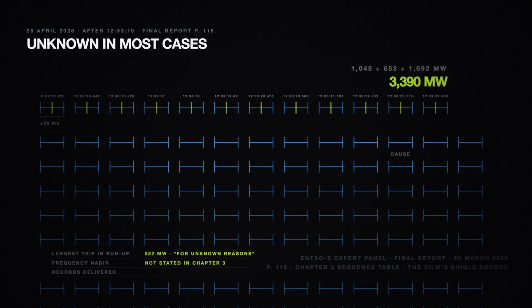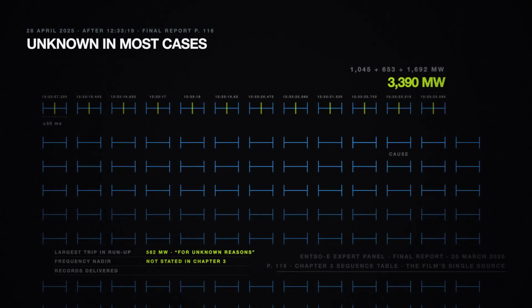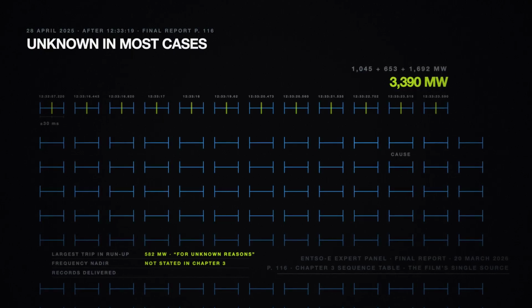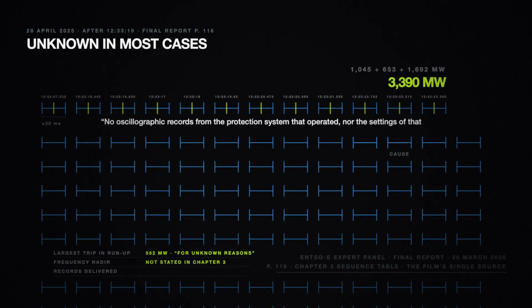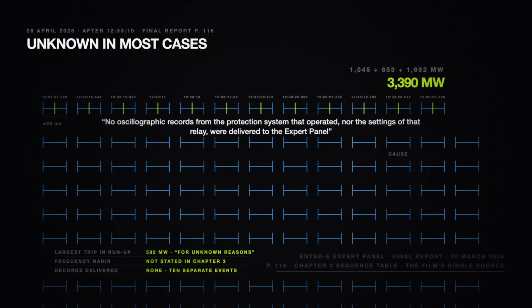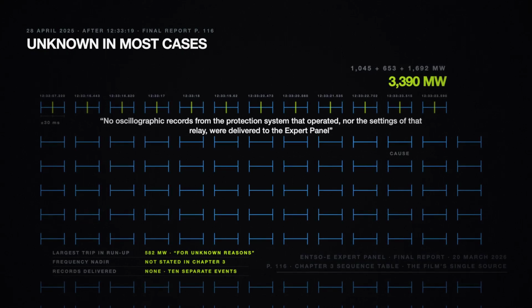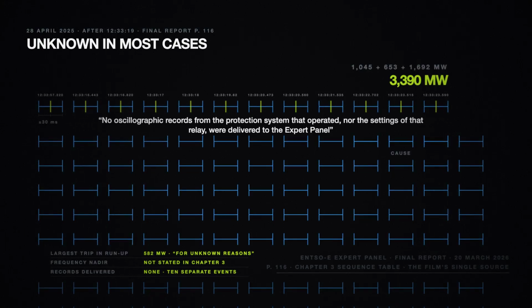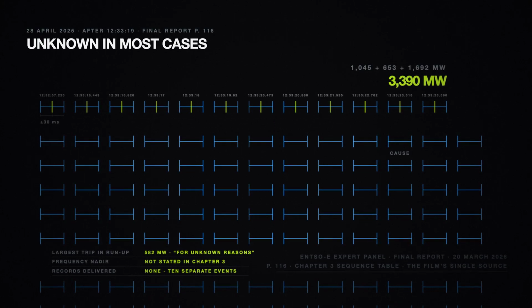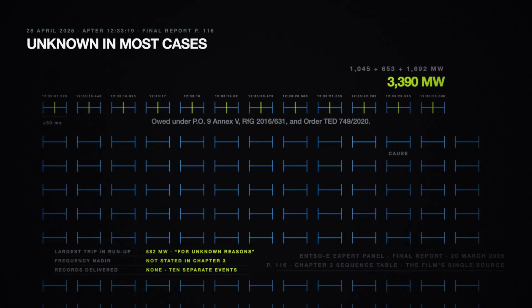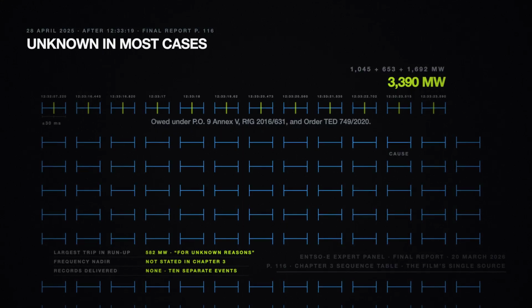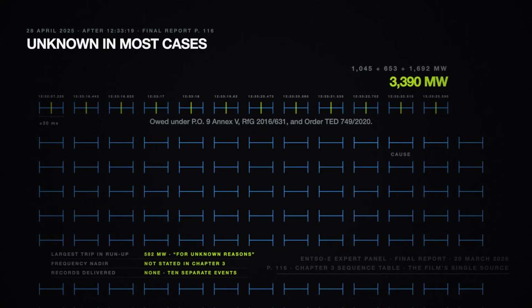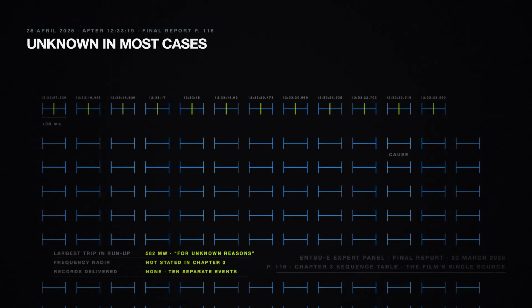This film rests on one document, the expert panel's final report of the 20th of March, 2026. The Spanish operator's account and the government committees were not read for it. And in that one document, for 10 separate events, a sentence recurs. No oscillographic records from the protection system that operated, nor the settings of that relay, were delivered to the expert panel. Those records are owed under Operating Procedure 9, Annex 5, under the European requirements for generators, and under a Spanish ministerial order of 2020. They were owed, they were not delivered.